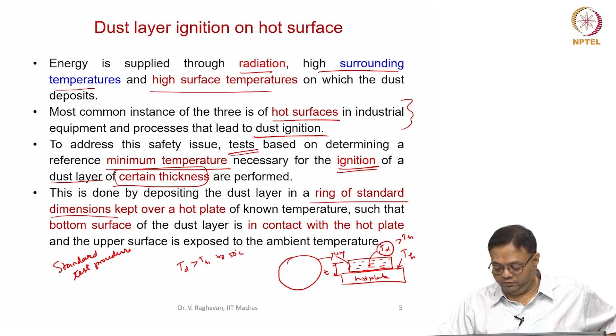Now, how to do this? There is a standard test procedure. You have a ring of standard dimensions. The front view will be like this, and you deposit the dust over this ring, which is kept on a hot plate. The hot plate surface temperature can be controlled. Now I put a thermocouple here to find the dust temperature and see whether, for this dust layer thickness T, and this TH, the dust temperature TD exceeds TH or not, causing spontaneous ignition. Basically, we need a condition where the dust temperature should be greater than TH by above 50 degrees centigrade. So this is the standard test procedure, based upon some ASTM or European standards.